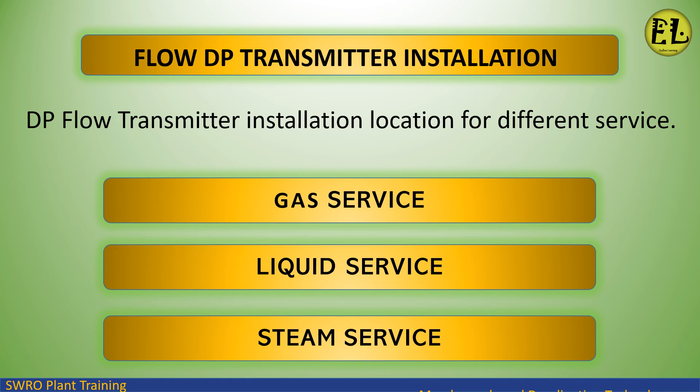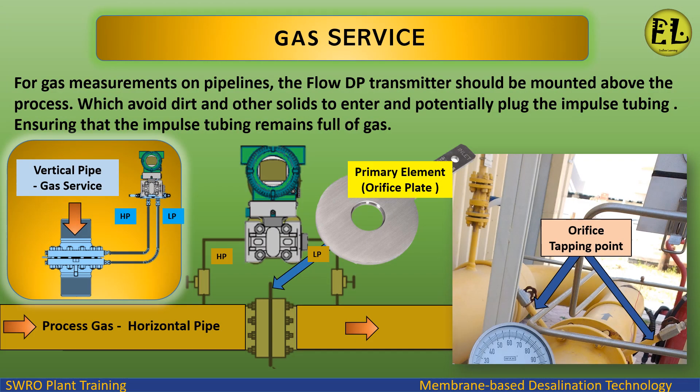For different services — gas service, liquid service, and steam service. For gas service, for gas measurements on pipelines, the flow DP transmitter should be mounted above the process to avoid dirt and other solids entering and potentially plugging the impulse tubing, ensuring the impulse tubing remains full of gas. DP flow meter installation for horizontal and vertical pipelines are shown.